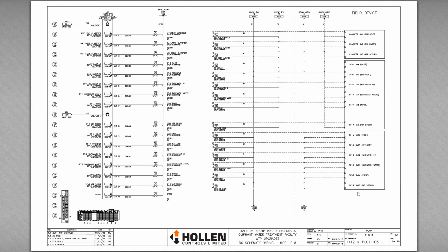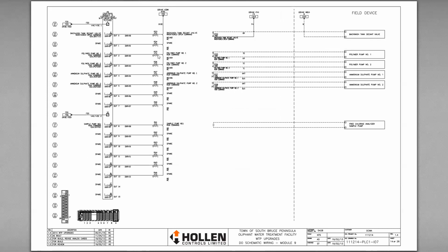Again, field devices for the clarifiers inside the panel. Inside the panel, we have more field devices. It looks like these ones, again, are supplied power. These ones are only using the contacts. These polymer pumps must send and receive that power themselves, so they must have power supply internally for their run commands.